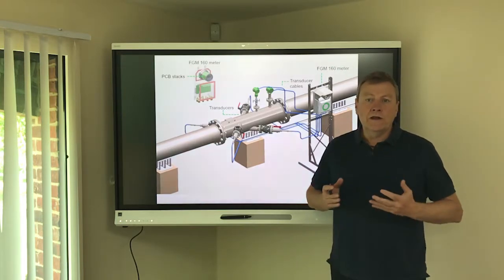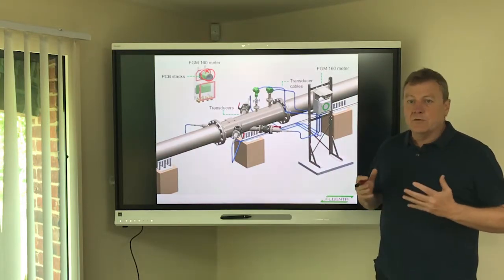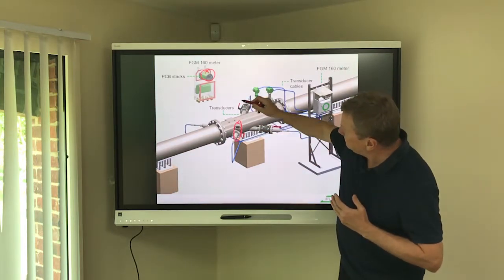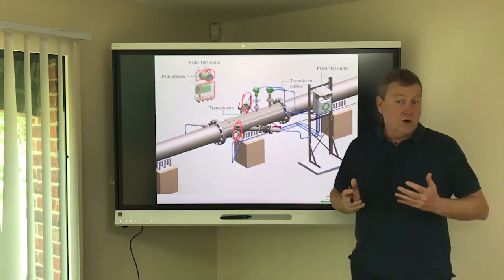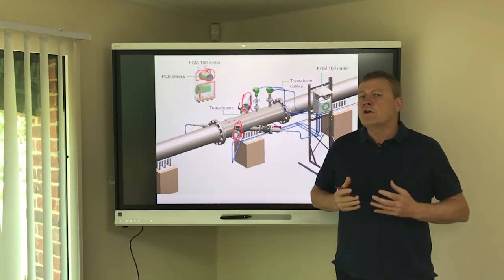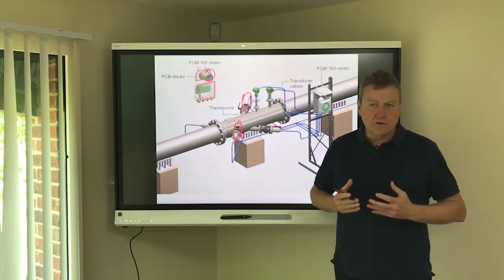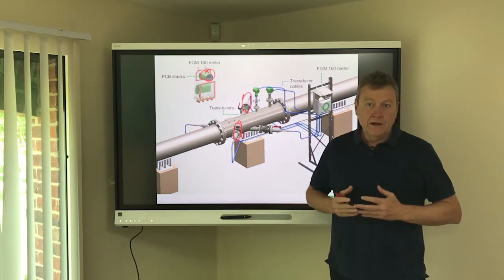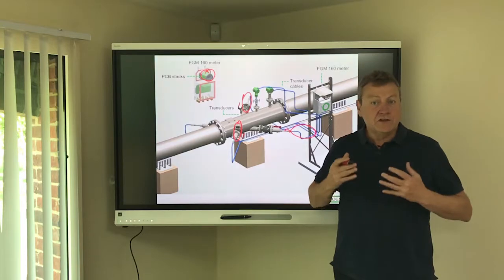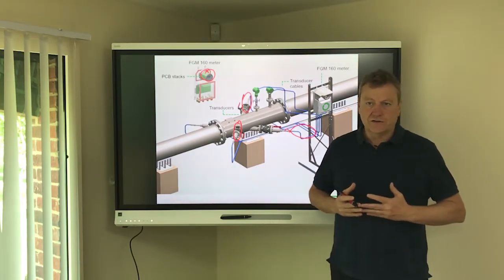Typical spares will include printed circuit boards for the flow computer together with associated seals and fuses. Spare transducers of the appropriate type — for example our standard transducer, high temperature transducer, or our 55 kilohertz transducers which are designed to facilitate measurement in flows of high CO2 content. Connection cables are also worth keeping on site, terminated with our Lemo connectors to facilitate a quick interchange on site.